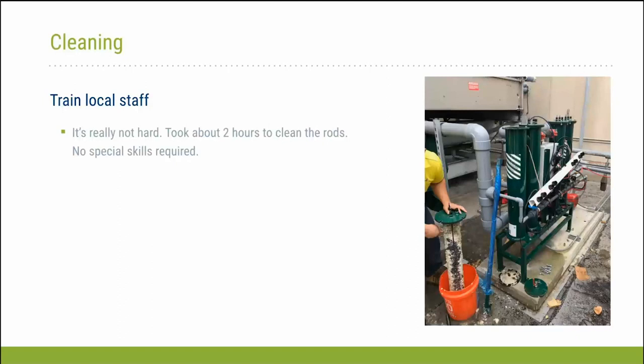The actual cleaning of the unit is not that difficult at all. The tan bar or rod that you see halfway down the right side of the unit in the picture there actually sits on top of the probes, on top of the reactor tubes, which are those green canisters Greg mentioned before. They power the tube and the insert, which are cathode and anode parts, if you will. The small diameter rod that you see in the foreground of the insert is the anode. In order to do the cleaning, you take off that power bar.